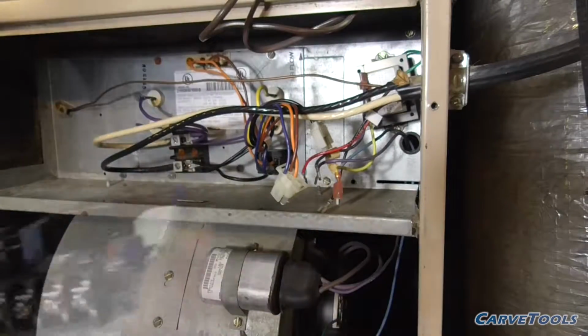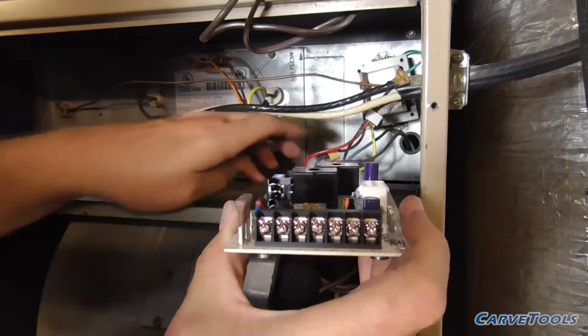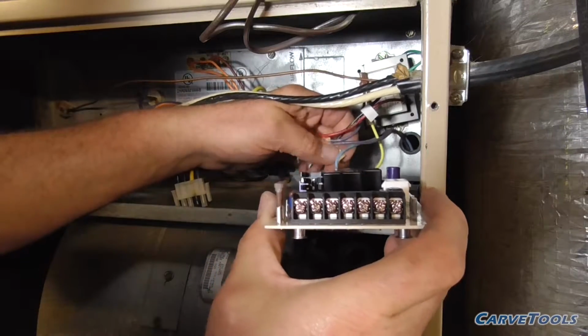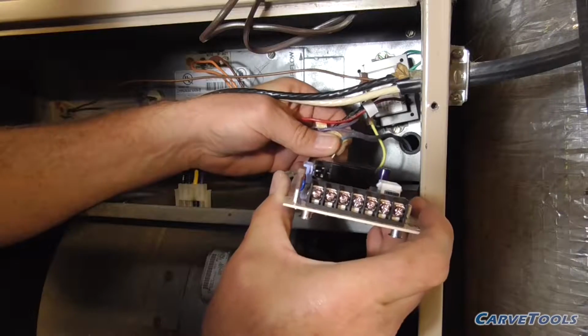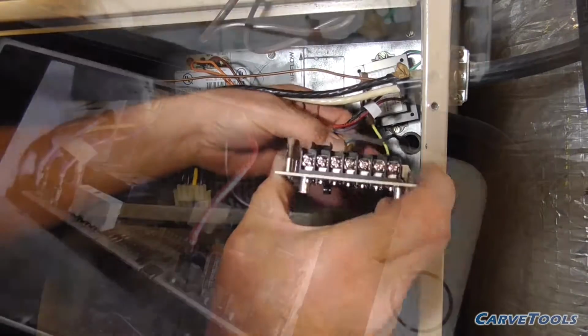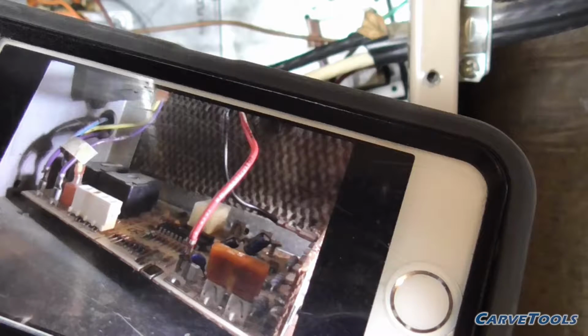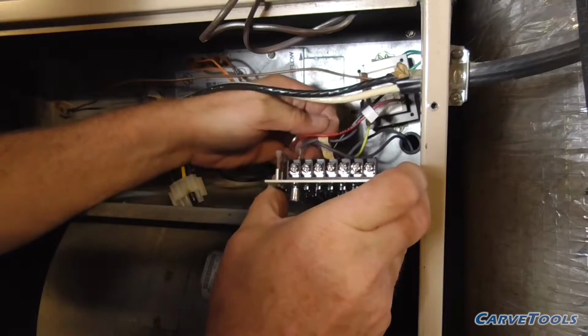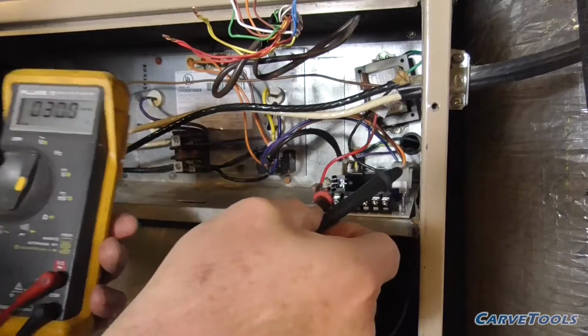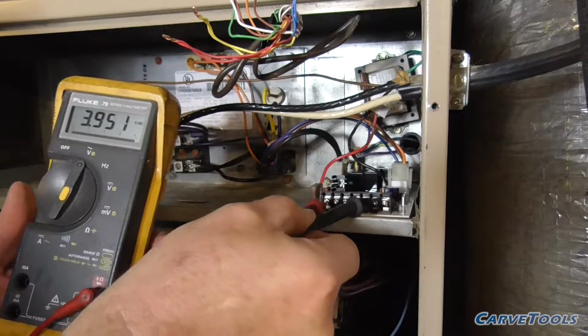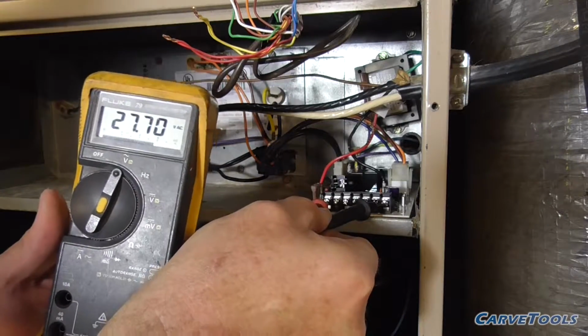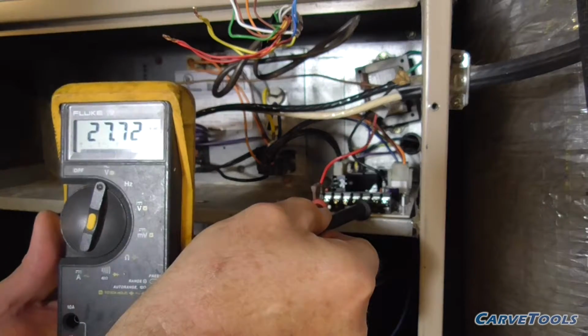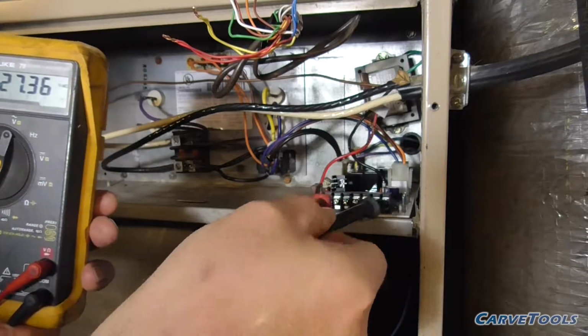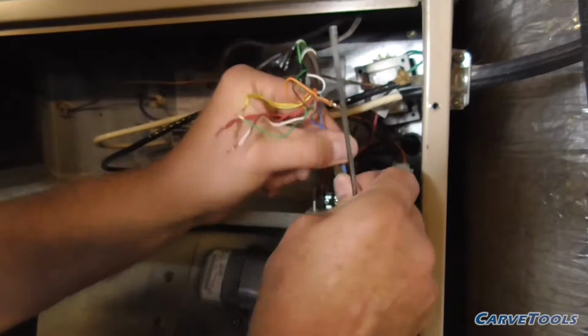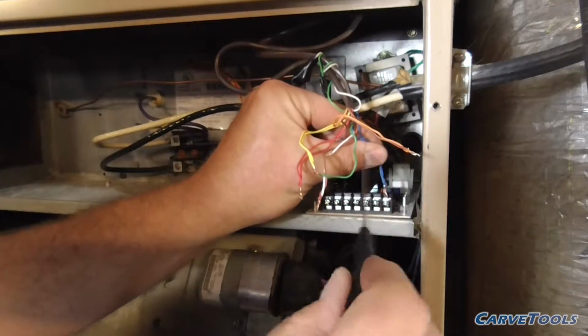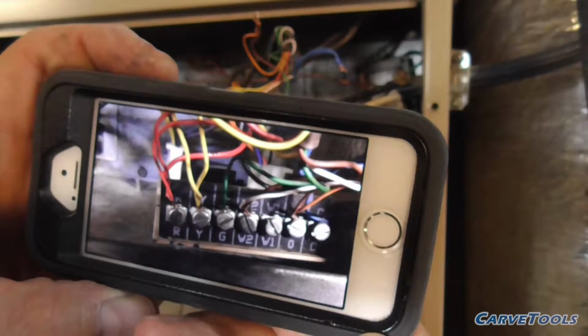I checked for the jumpers to be in the correct location. Here I connect all the wires except the control wiring. Remember to refer to your photo you took earlier and double check your connections. I turned on the 220 volt breaker and checked for control voltage. And there it is, 28 volts AC. This is what we were looking for.